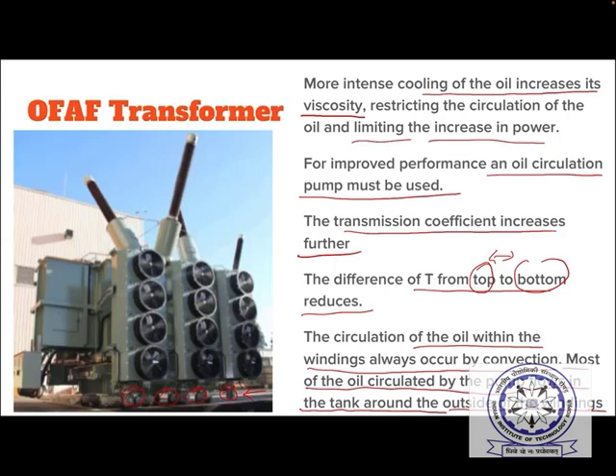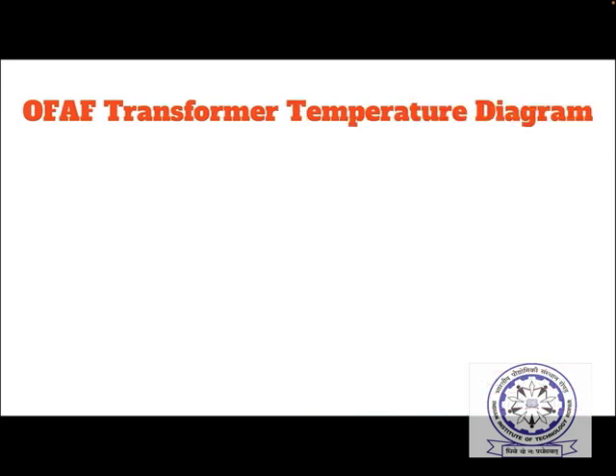So this is about the OF-AF transformer. In this, oil is circulated, but within the windings oil will not circulate using the pumps; it happens through natural convection only. A little bit of difference may be there. As per the temperature diagram of the OF-AF transformer, it is like this actually.